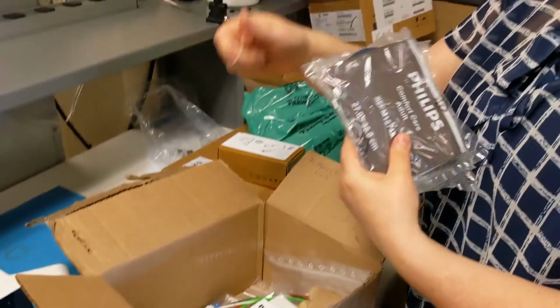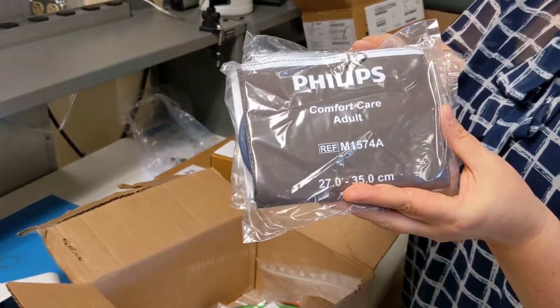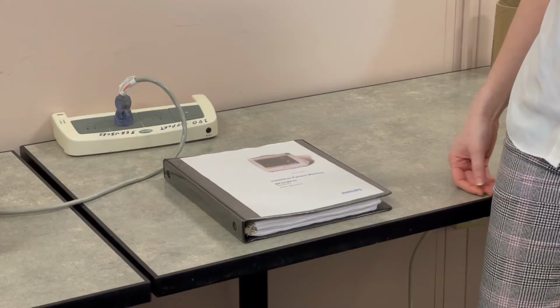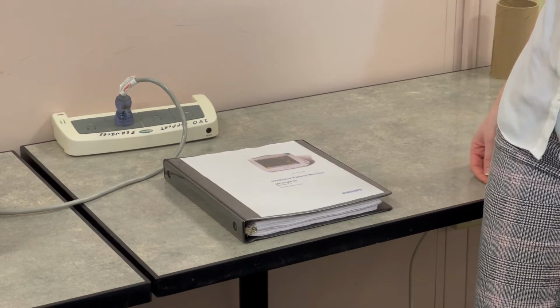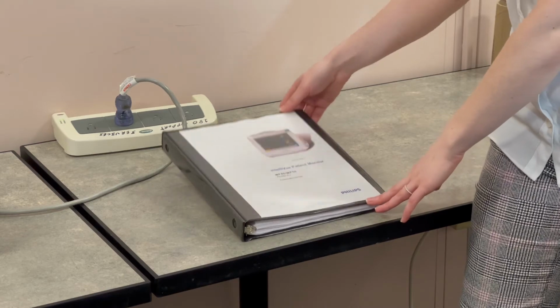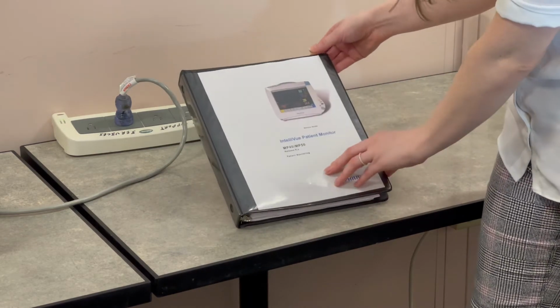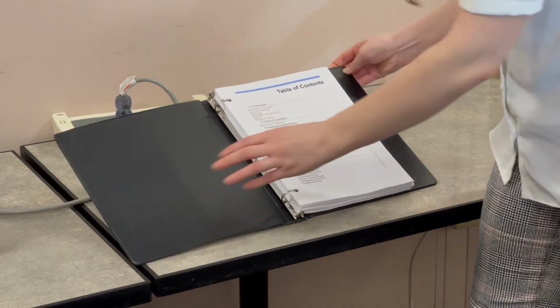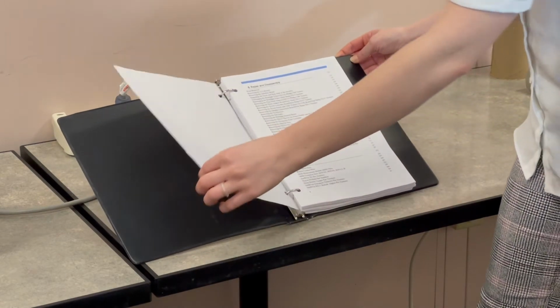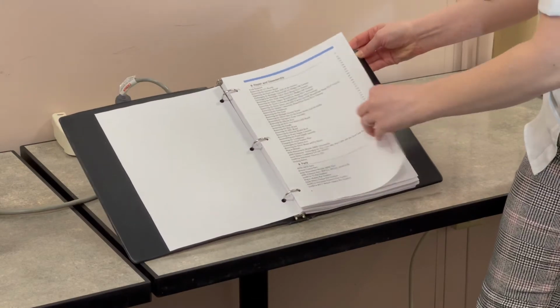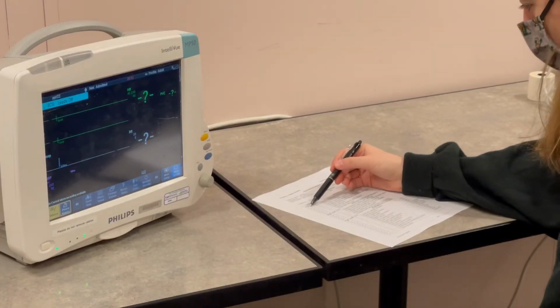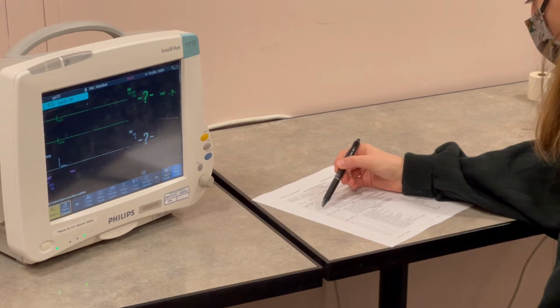Ensure that the power cable matches the electrical connection in the clinical area where the device will be used. Make sure both the user manual and the service manual are included in the box. Some vendors provide the manuals on CD or online. Verify that the documentation is accessible. Read through the user and service manuals provided with the patient monitor to familiarize yourself with them. Note any discrepancies or any damage to the device or accessories that may have happened during shipping and report it right away to the supplier and your colleagues who need to know, such as the purchasing or stores manager, as well as the care provider.